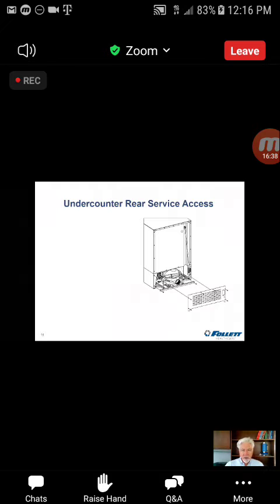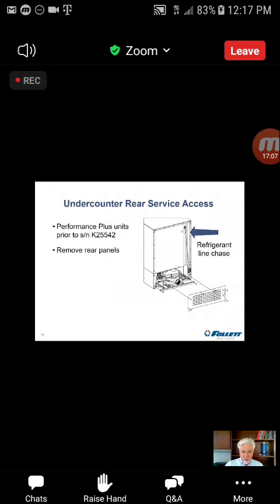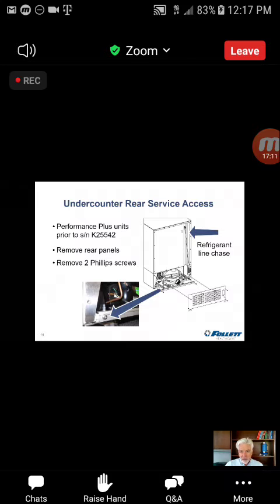Now, the securement method that we just saw there is what we're using today. It has changed a little bit over time as our product has evolved. On previous models of Performance Plus, it's a little bit different. So we still have that rear panel and that chase that enables you to pull the condensing unit partially out for service work. But this is where we talk about serial number breaks. When we make a significant change, we note the serial number. So prior to this number, K25542, you still remove the rear panels, but there are two Phillips head screws that are horizontal. So it's the same principle, just secured a little bit differently, instead of the vertical bolts, which, by the way, is on the original units we call legacy units. Those were vertical bolts as well that secure the condensing unit to the base of the unit.